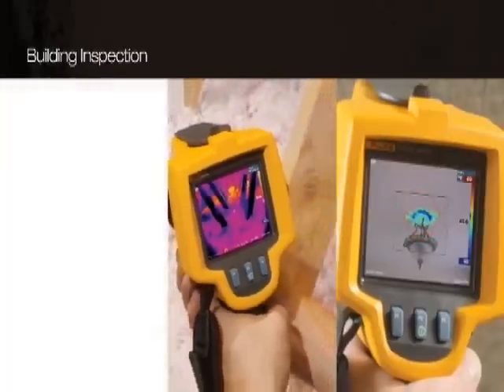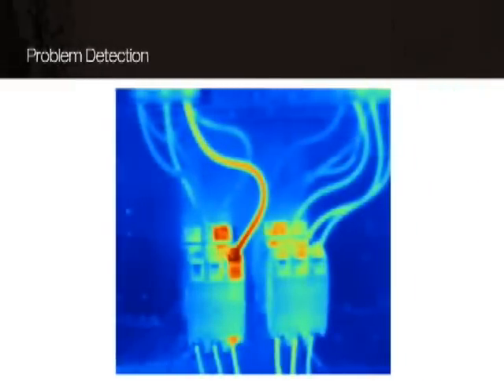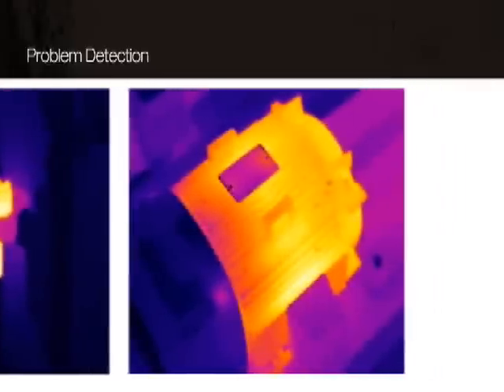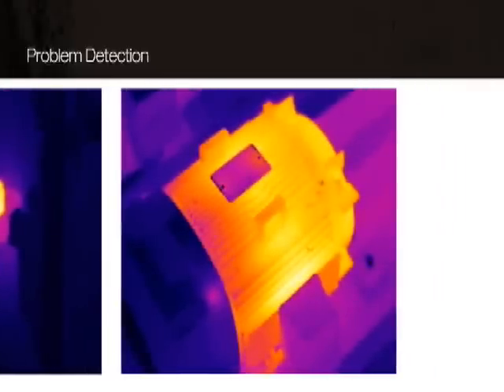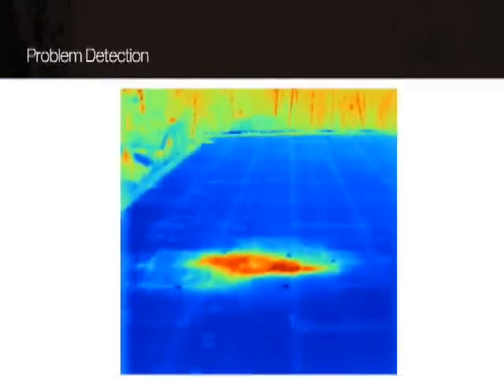Here are a few more examples where a thermal imager can help detect problems: wiring mistakes in relays and switches, faulty steam traps, issues in motors or pumps, or moisture in low slope roofs.